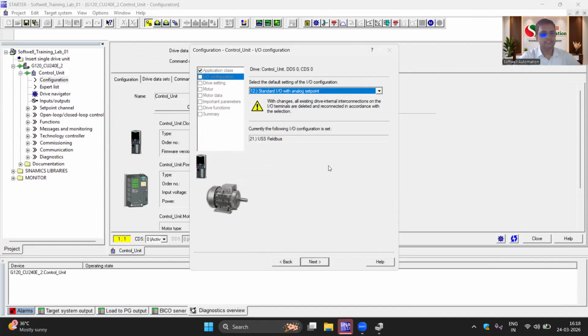The existing setting was 21, meaning our VFD is currently activated for networking, i.e., field bus, USS field bus — meaning either the Modbus protocol or Siemens' proprietary USS protocol. If you're a Siemens VFD user, you can use USS, and USS standard blocks are available by default as a library in TIA. Now I'll click next.